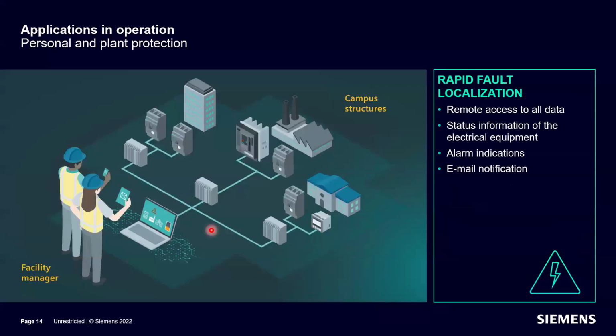Now, fault localization - let's say you have sensors like ACB and MCCB, and it has got a tripping because of certain reasons. It can remotely give you data on the status information, and if it has tripped, on which fault. The alarm indication will be there on the web page itself, and you will also get an email notification. So it is easy to localize if something has tripped on a certain fault.